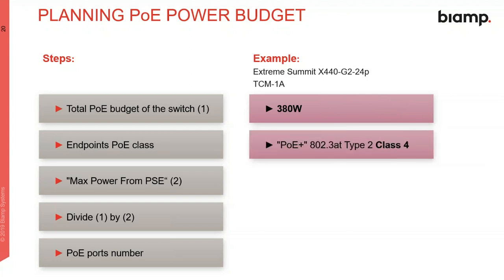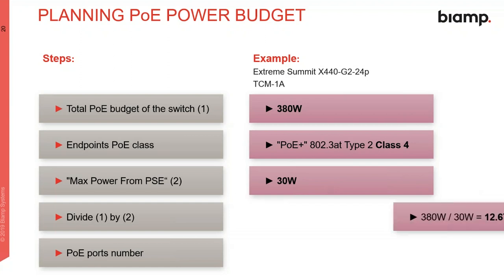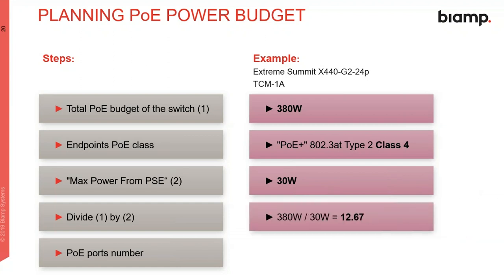The TCM1A is a PoE Plus device. It's an 802.3AT Type 2 Class 4, and that's information you can find in the spec sheets, and that should be available for all PoE devices out there. It should tell you what class it is. So we know by that class that it's going to want 30 watts of PoE. So we do the math and we come up with 12.67. We can't have 0.67, so that's going to limit us to 12 in this particular case.